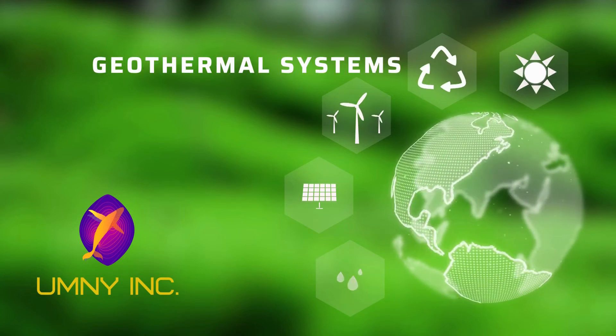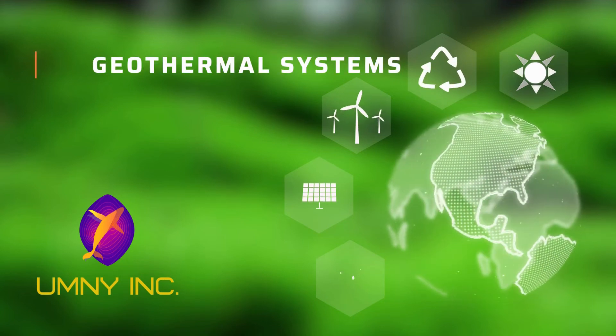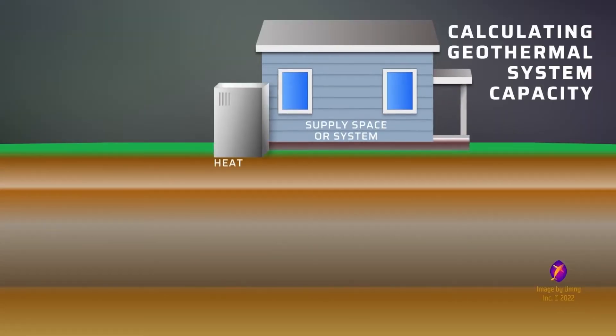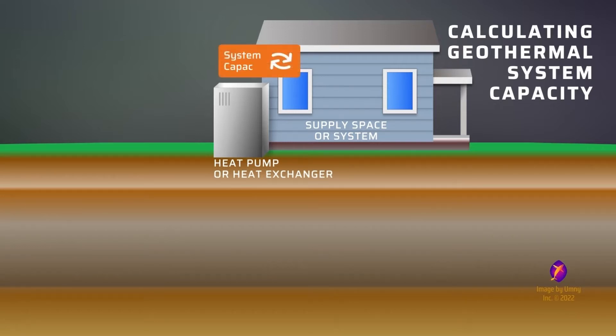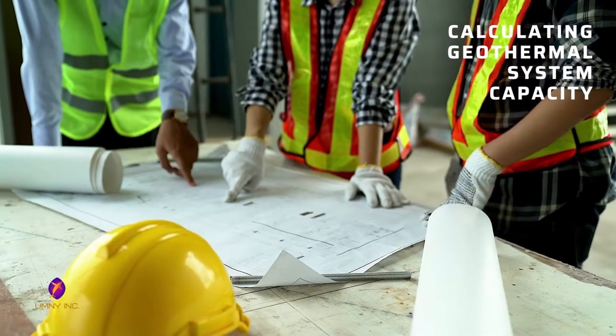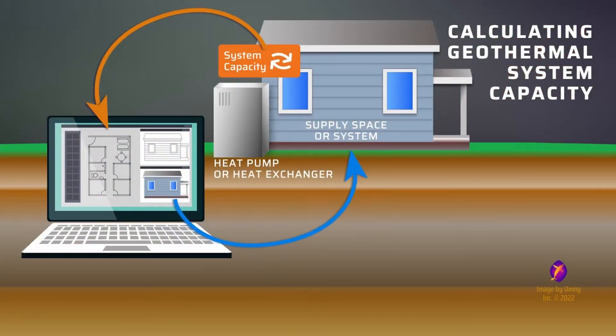Geothermal systems are a great way to deliver renewable and efficient heating and cooling to a space such as a building or a system such as a domestic hot water tank. This energy may be transferred to the target area by a ground source heat pump or a heat exchanger. The amount of usable thermal energy this equipment supplies is called the system capacity. To design a reliable geothermal system, this system capacity needs to be accurately predicted before it is even built, so that the equipment can be sized properly for the needs of the supply space or system.